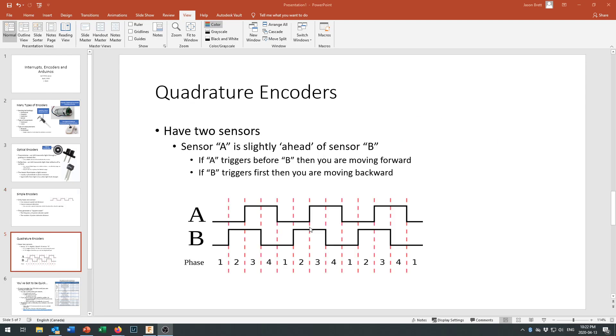Quadrature encoders are pretty much the industry standard — if you go out and ask somebody for an encoder, you'll probably get a quadrature encoder. That's a fancy name for saying you're getting two sensors: channel A and channel B. The beautiful thing is you can use it as just a simple encoder — if you only look at channel A, you can measure pulse length to figure out speed, and count the pulses to measure how far you've gone without doing anything with channel B.